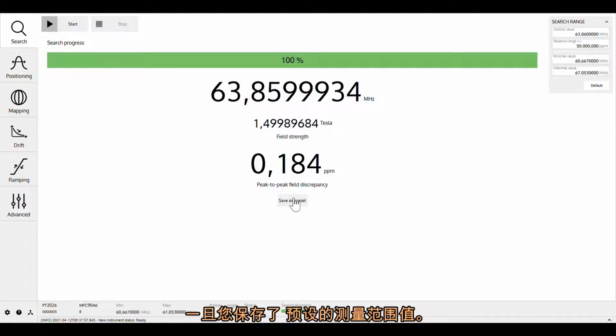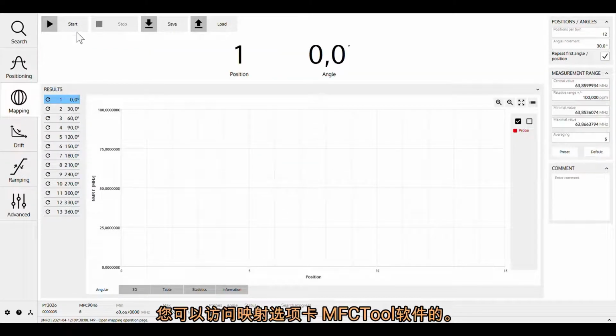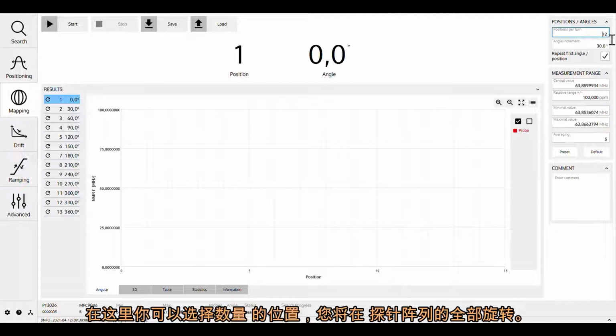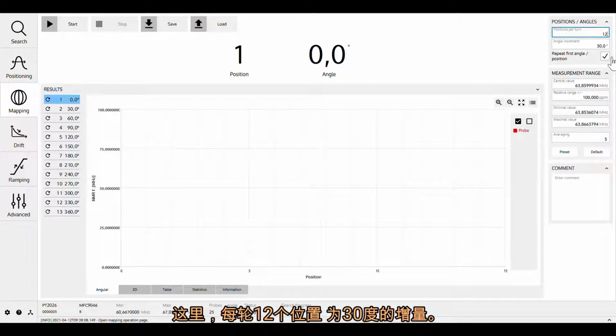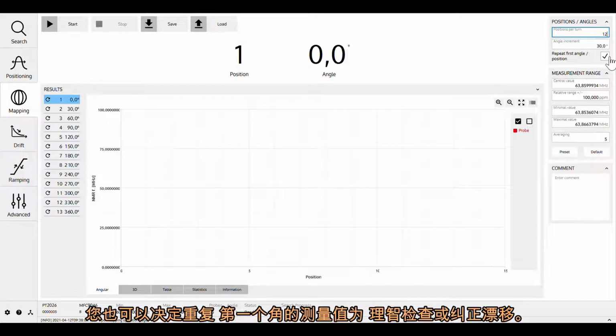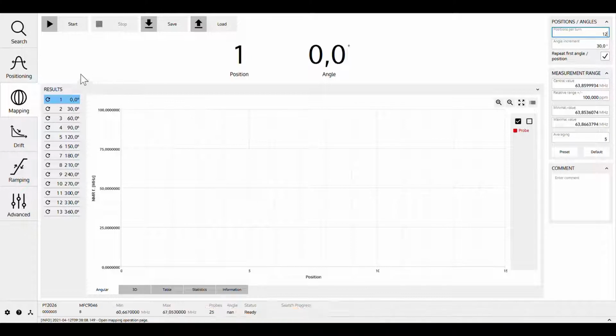Once you have saved the preset measurement range, you can access the Mapping tab of the MFCTool software. This is where you can select the number of positions you will measure during the full rotation of the probe array. Here, 12 positions per turn for an increment of 30 degrees. You can also decide to repeat the measurement of the first angle as a sanity check or to correct for drift. You are now ready to collect 13 sets of measurements.